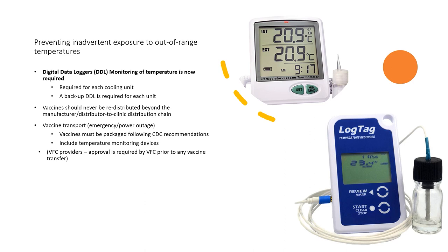CDC recommends a specific type of temperature measuring device called a digital data logger, or DDL. A DDL provides the most accurate storage unit temperature information, including details on how long a unit has been operating outside the recommended temperature range, referred to as a temperature excursion. Unlike a simple minimum-maximum thermometer, which only shows the coldest and warmest temperatures reached in a unit, a DDL provides detailed information on all temperatures recorded at preset intervals.